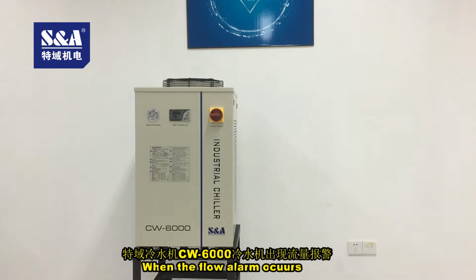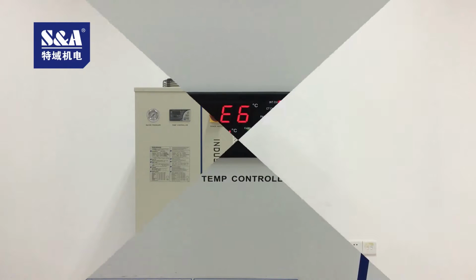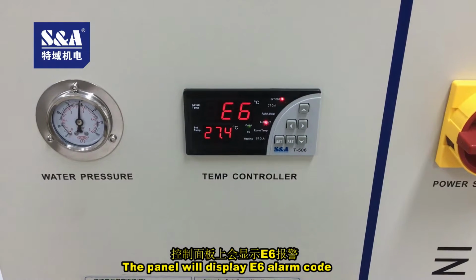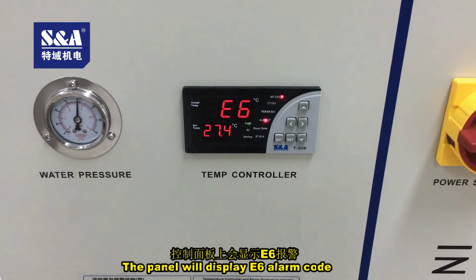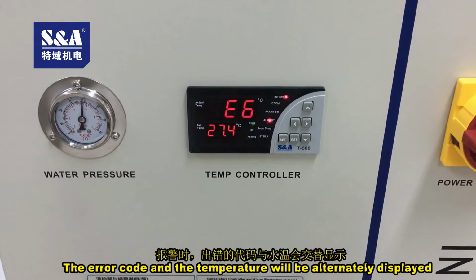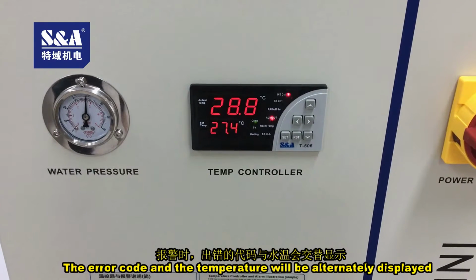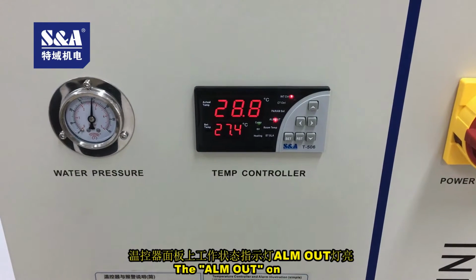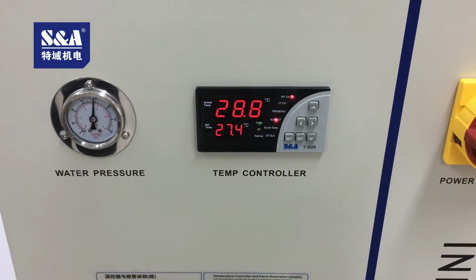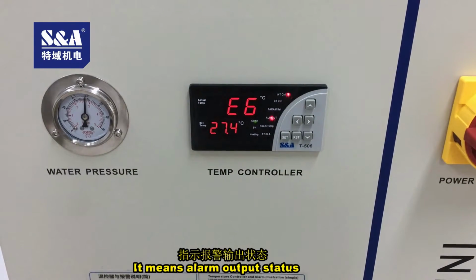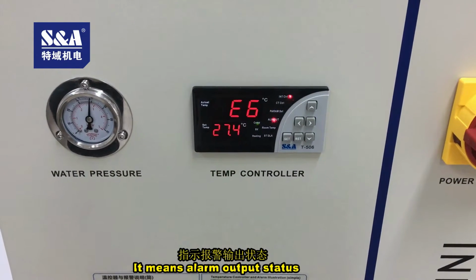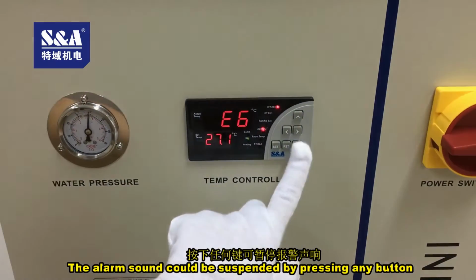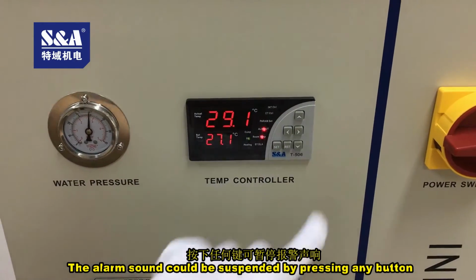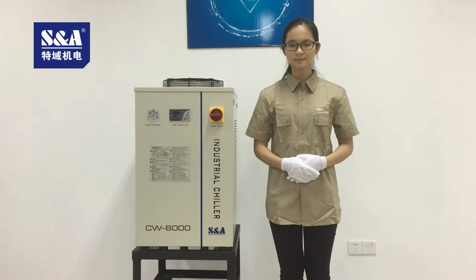CW-6000. When the flow alarm occurs, the panel will display the E6 alarm code. The error code and the temperature will be alternately displayed. The alarm out on means alarm output status. The alarm sound could be suspended by pressing any button.